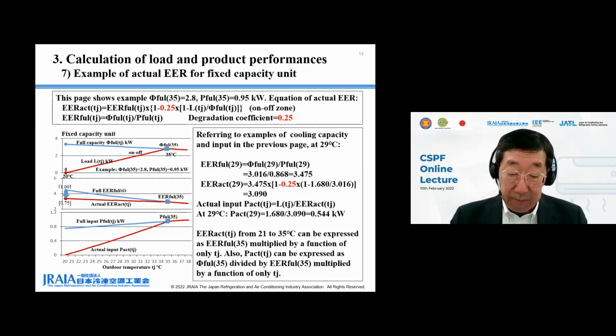This page shows calculation example of actual EER for fixed capacity unit in the case of 35 degrees C full capacity 2.8 and full input 0.95 kilowatt. Actual EER in on-off zone can be calculated by the equation shown here.